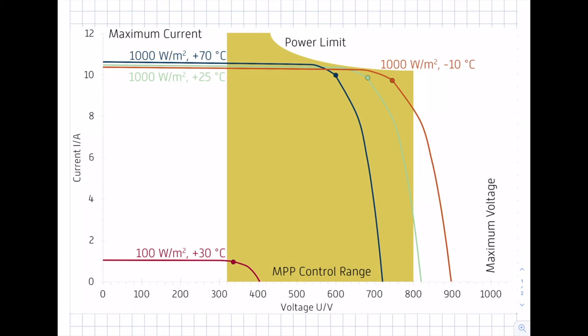Finally, we consider a fourth condition: just 100 watts per square meter irradiance with a module temperature of plus 30 degrees Celsius. You can see the different slope of the curve — smaller irradiance means smaller current. But still, the MPP must be within the MPP control range of the inverter.